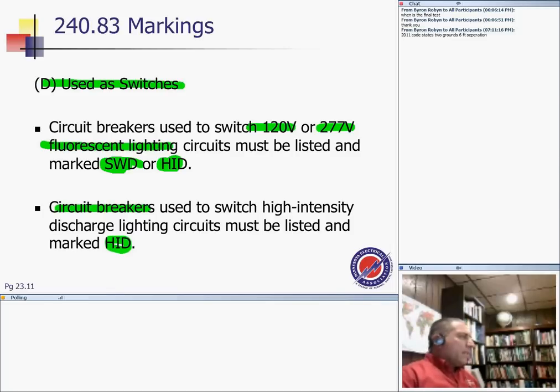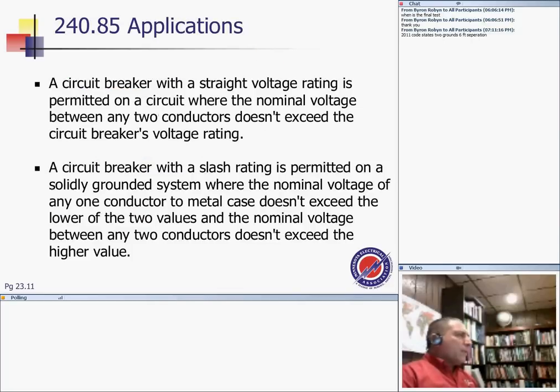If you don't rate the circuit breakers to handle them, you can damage your circuit breaker's functions. So if you have a short circuit, they might not trip. How can I damage a circuit breaker? If I have a short circuit, I need the circuit breaker to wake up and trip, so it must not fail to trip. And guys, that's about using the circuit breakers as switches, and you're jumping through the applications.